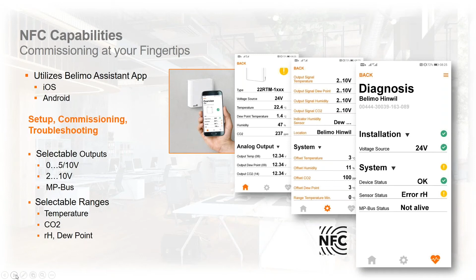It's a very useful tool that helps with installation and commissioning. The outputs you're able to select through the NFC app are 0 to 5 volt, 0 to 10 volt, 2 to 10 volt, or MP bus right now. You also have fully selectable temperature ranges on the temperature and CO2 side, and you can choose between relative humidity or dew point outputs on the humidity side.